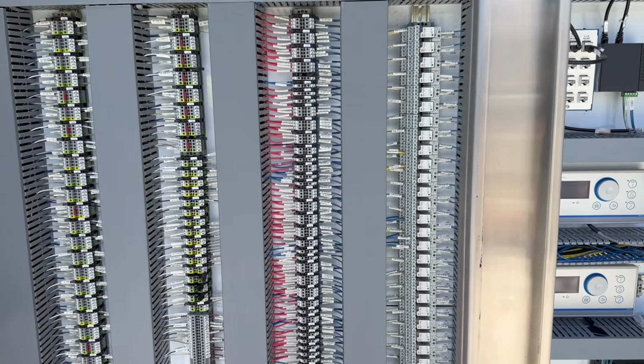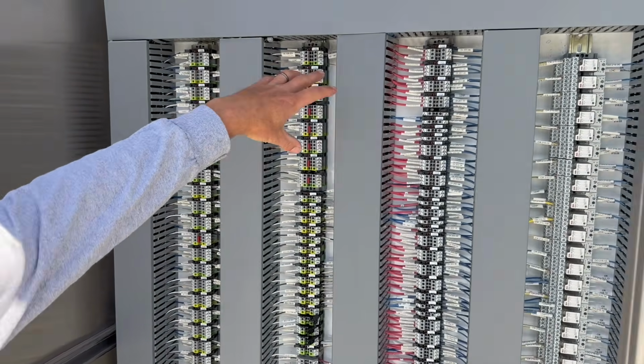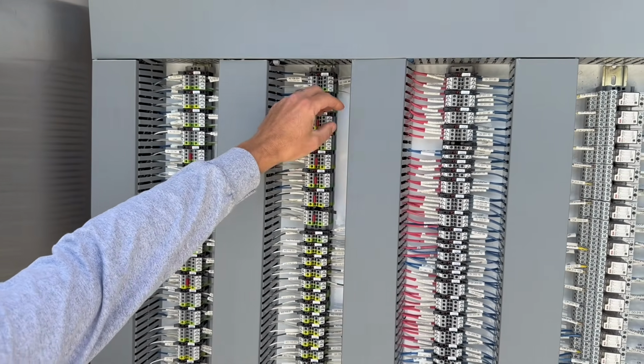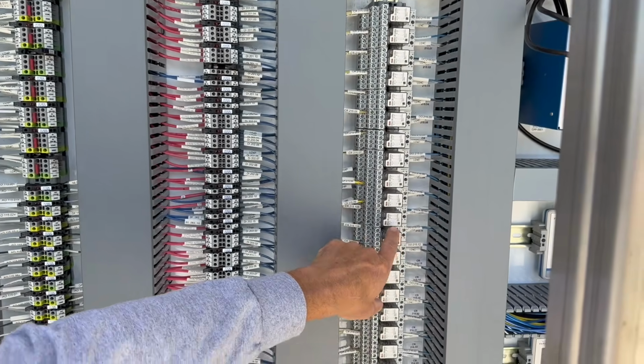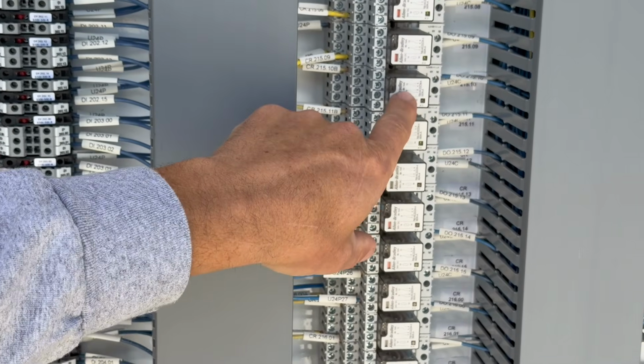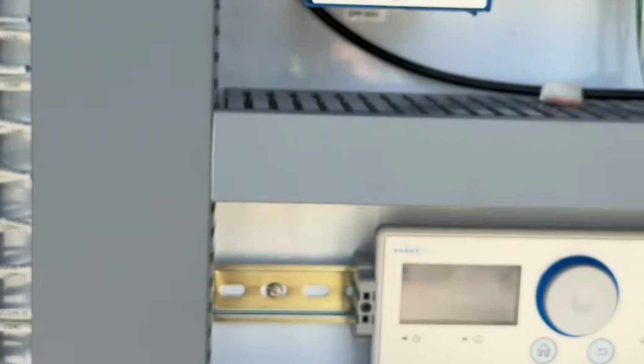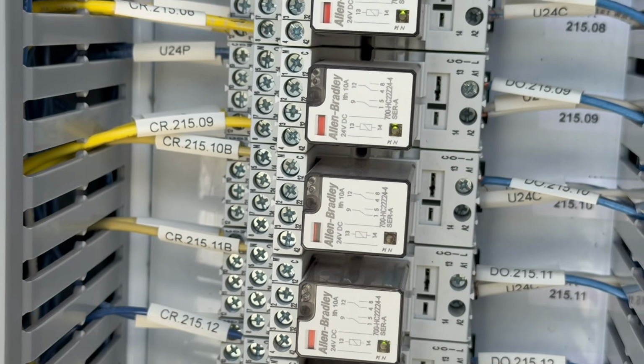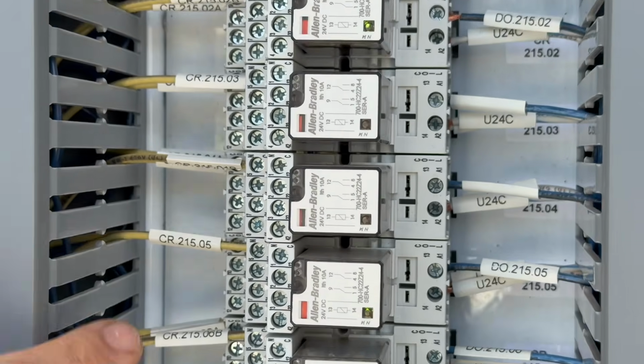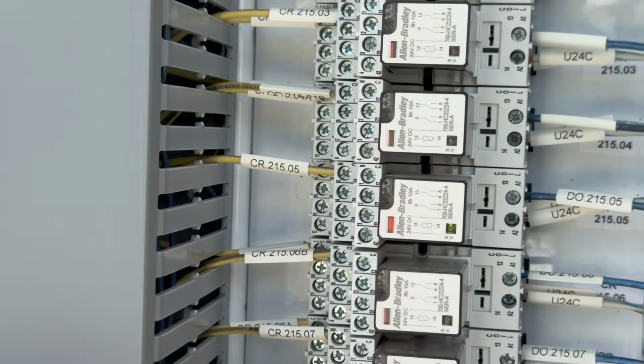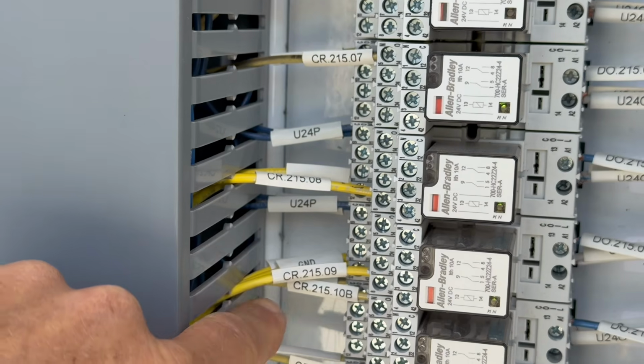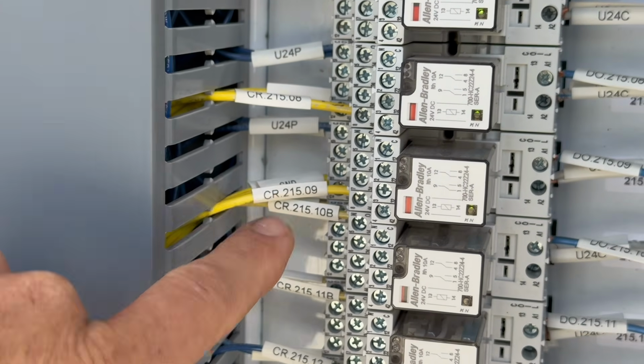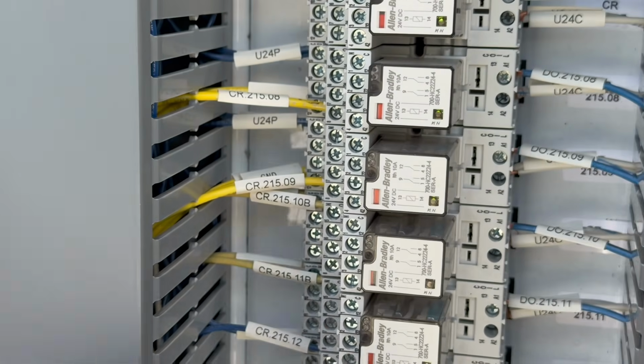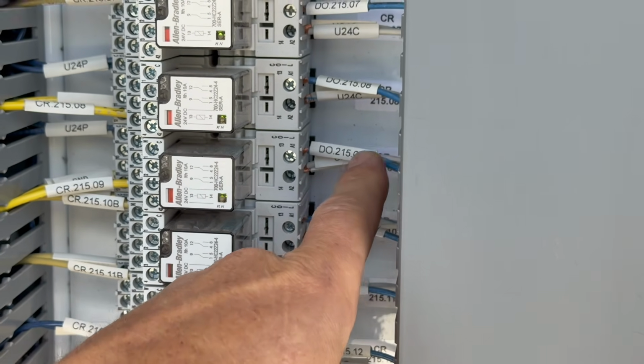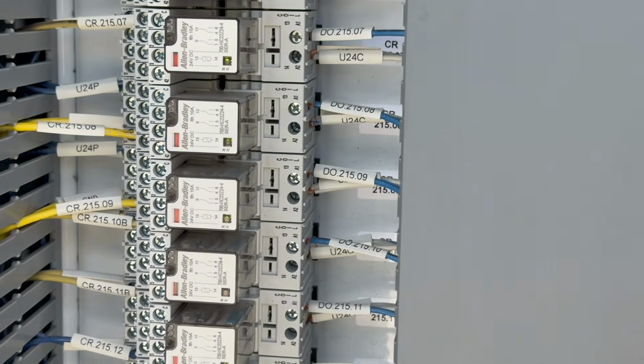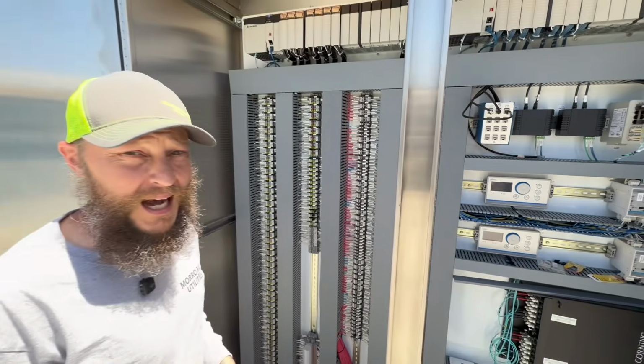And are these run by fuses, relays? What's going on? Yeah, so there are some fuses in here for things that need protection. A relay might look like this. There's lots of different form factors for them, but this one's called an ice cube relay. So the relay is here, in the socket, and speaking of the relays, notice there's wire color here. The yellow wire is foreign voltage in this particular panel. So it's voltage that's outside. Even if I have this de-energized, this yellow wire is still going to be energized. And then blue over here is a positive 24 volt DC. Most modern panels are low voltage, so we can work on them hot.